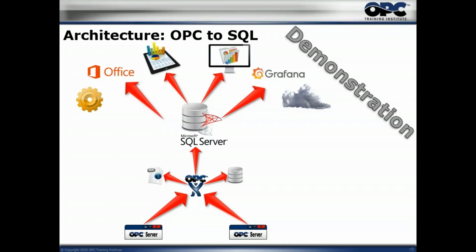So, John, what you're asking is, would there be another record for memory if the quality changes? Yes, absolutely. There's a record every time there's a change, and the change can be either a value, quality, or a timestamp. It just so happens that the timestamp didn't change at all from the OPC server. So that's why there's no change.